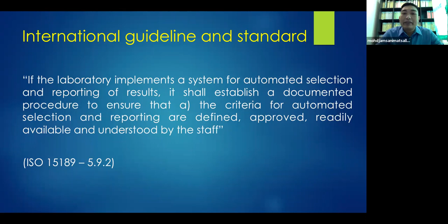So what actually is auto-verification? Auto-verification is automated result verification, because traditionally what we do is based on a mental algorithm that we use to decide whether the result can be released or not. It is also based on single or group of analytical results. But the most important thing is that auto-verification helps us to identify analytical errors, pre-analytical errors, and post-analytical errors, because this is the final step that we can do before a result is released.